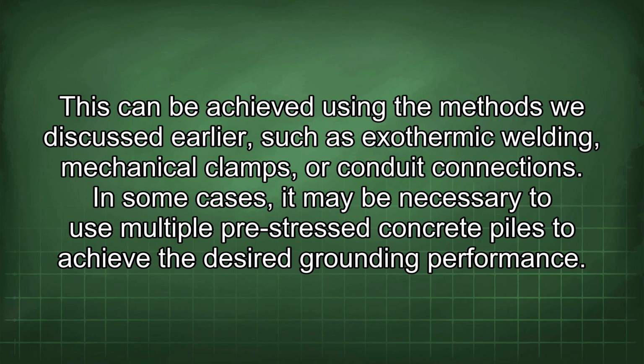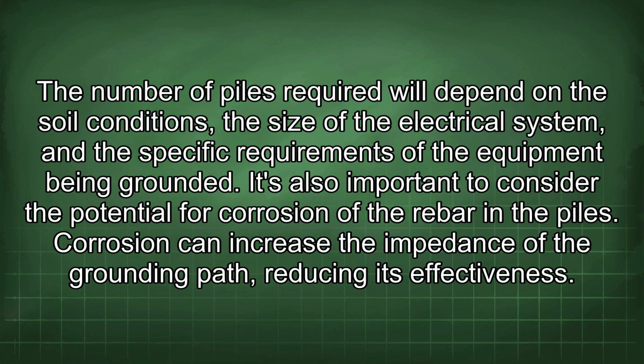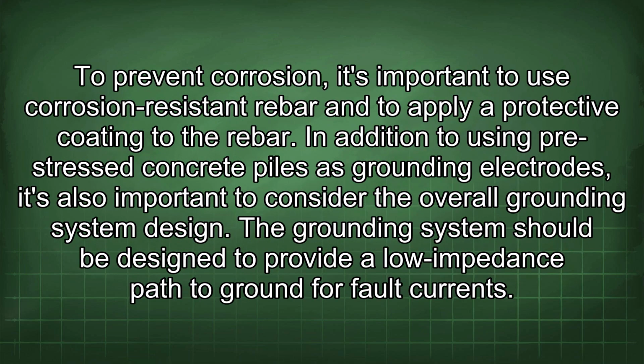In some cases, it may be necessary to use multiple pre-stressed concrete piles to achieve the desired grounding performance. The number of piles required will depend on the soil conditions, the size of the electrical system, and the specific requirements of the equipment being grounded. It's also important to consider the potential for corrosion of the rebar in the piles. Corrosion can increase the impedance of the grounding path, reducing its effectiveness. To prevent corrosion, it's important to use corrosion-resistant rebar and to apply a protective coating to the rebar.